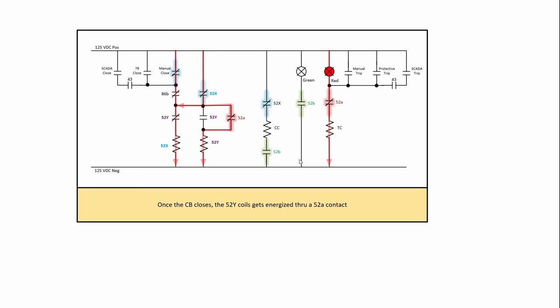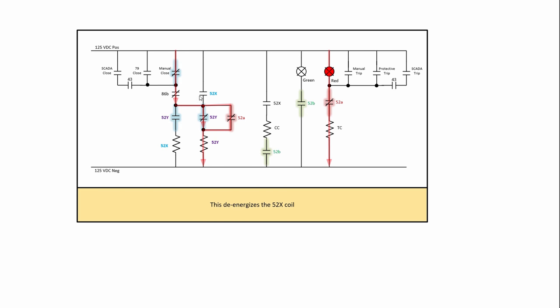So the 52Y now gets picked up, energizing that. And when it picks up, it changes state for its contacts and that will then take power off or current through the 52X contact. But importantly, the 52Y seals itself in. So now what happens is we have the 52Y sealed in through the parallel combination of the 52A and the 52Y. So when this thing closes, it seals itself in and that prevents you from energizing that 52X.